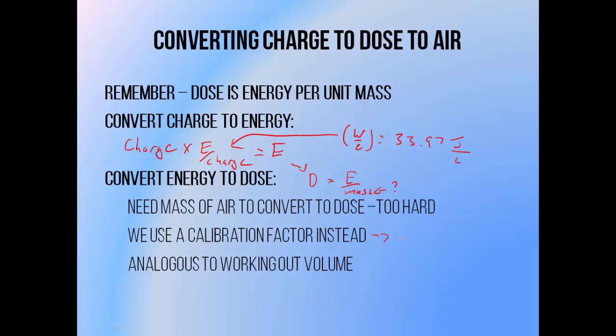This involves sending our ion chamber off to a primary standards lab, where it's exposed to a known amount of radiation as determined using a primary standards dosimeter like a graphite calorimeter or a cavity ionization chamber. And the ratio of delivered dose to measured charge is determined. This is the calibration factor.